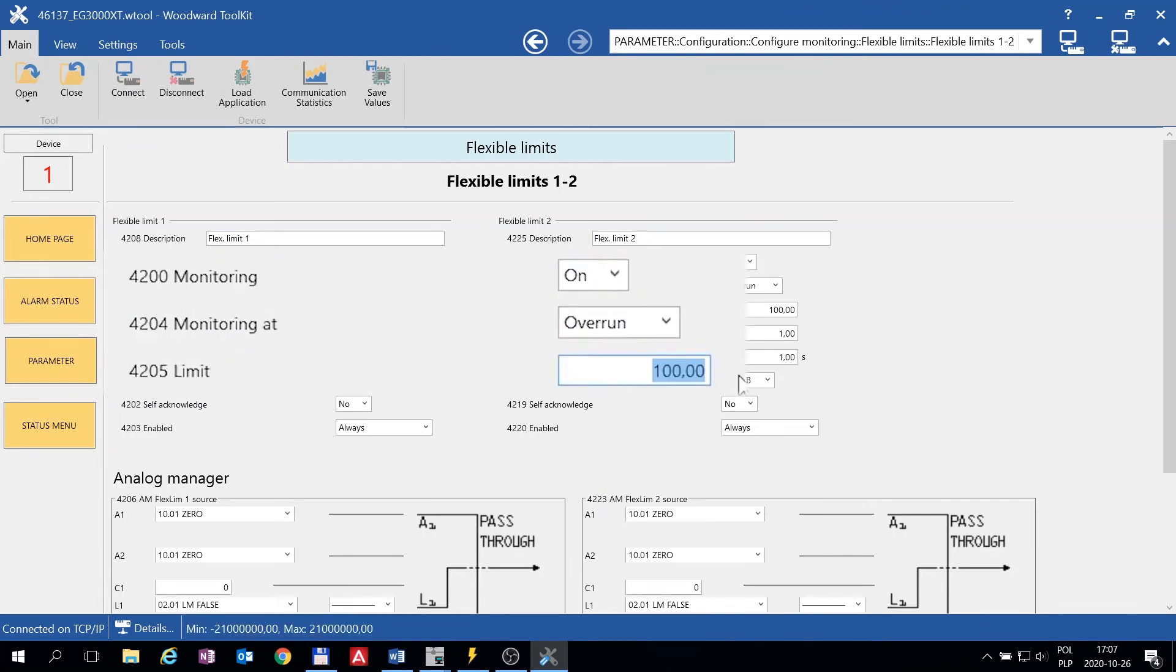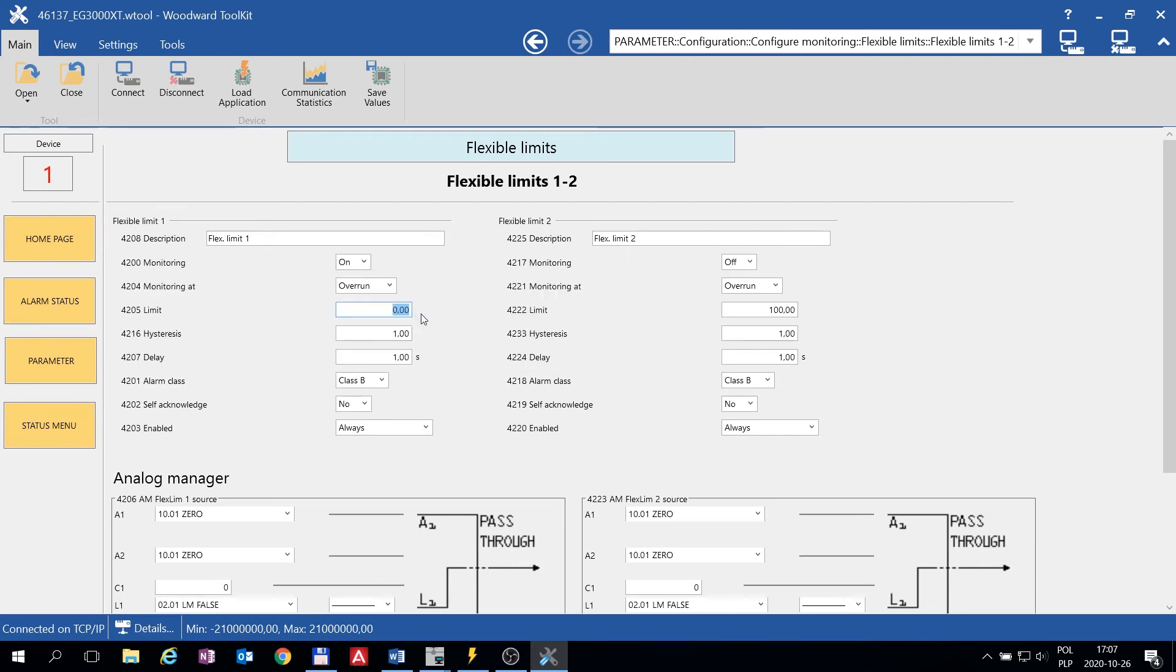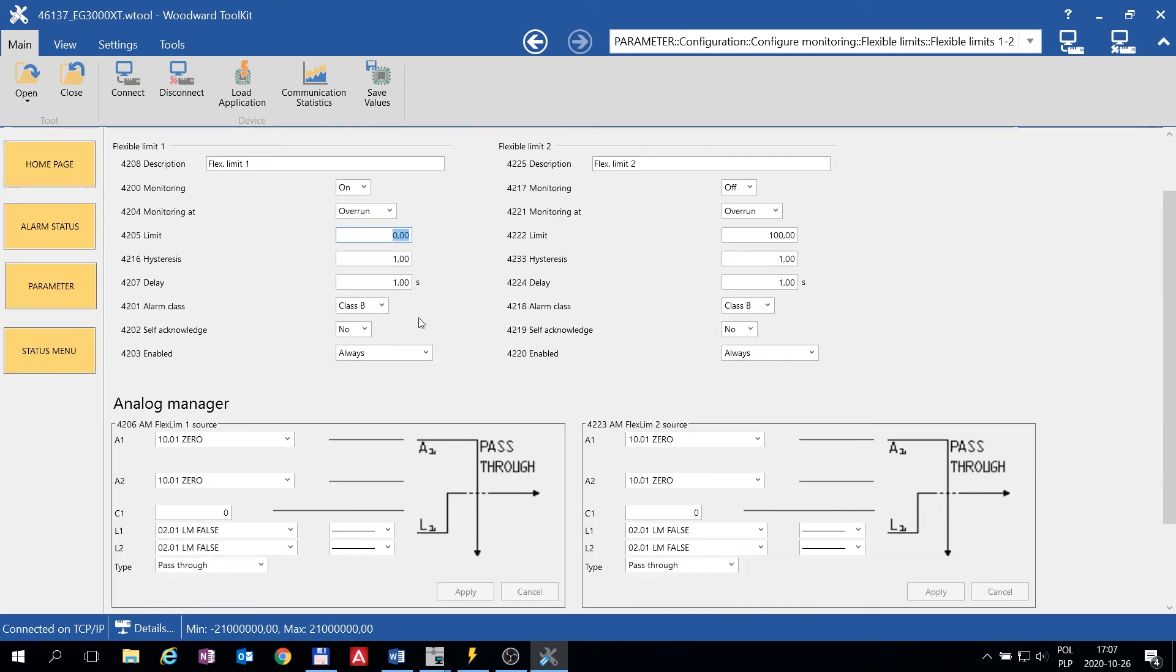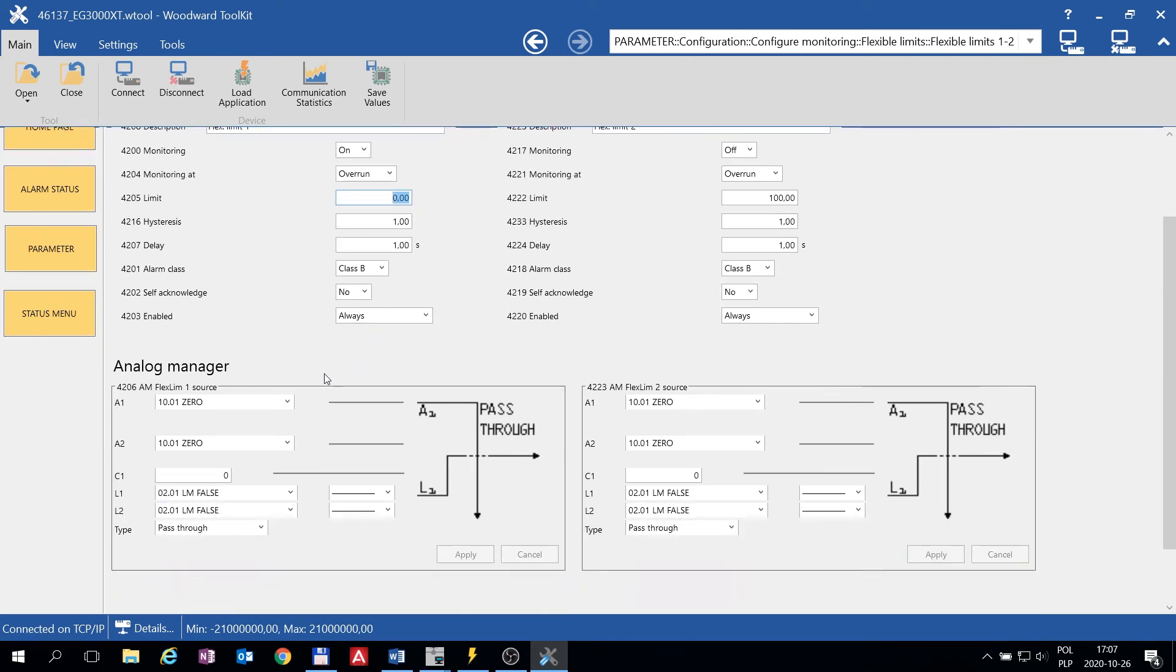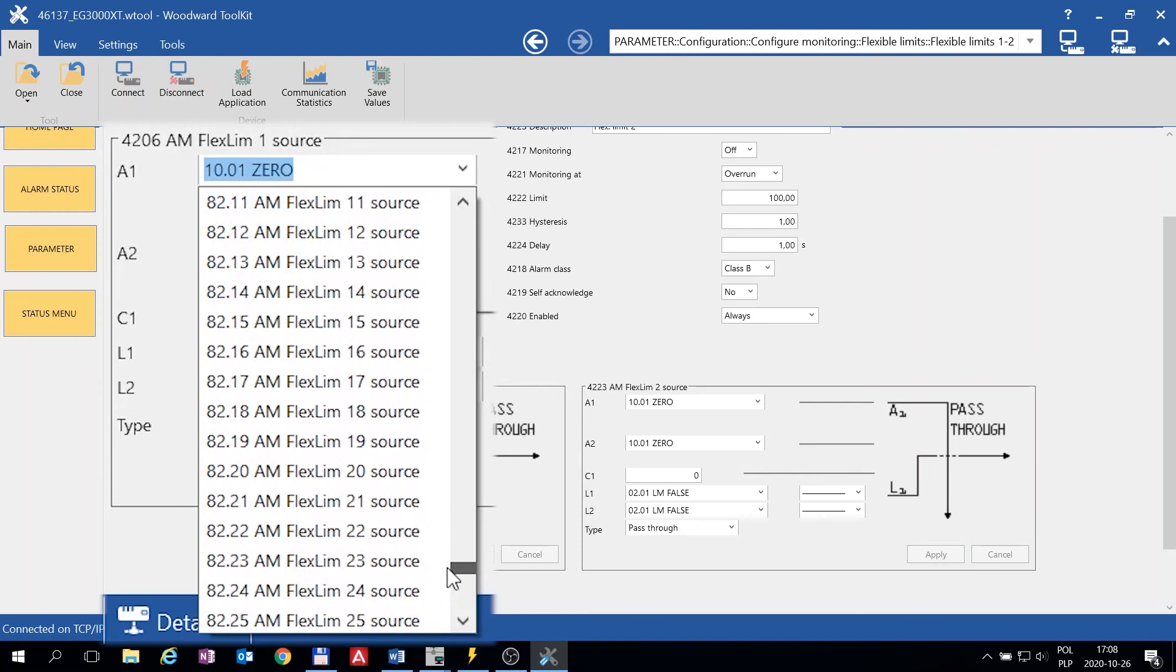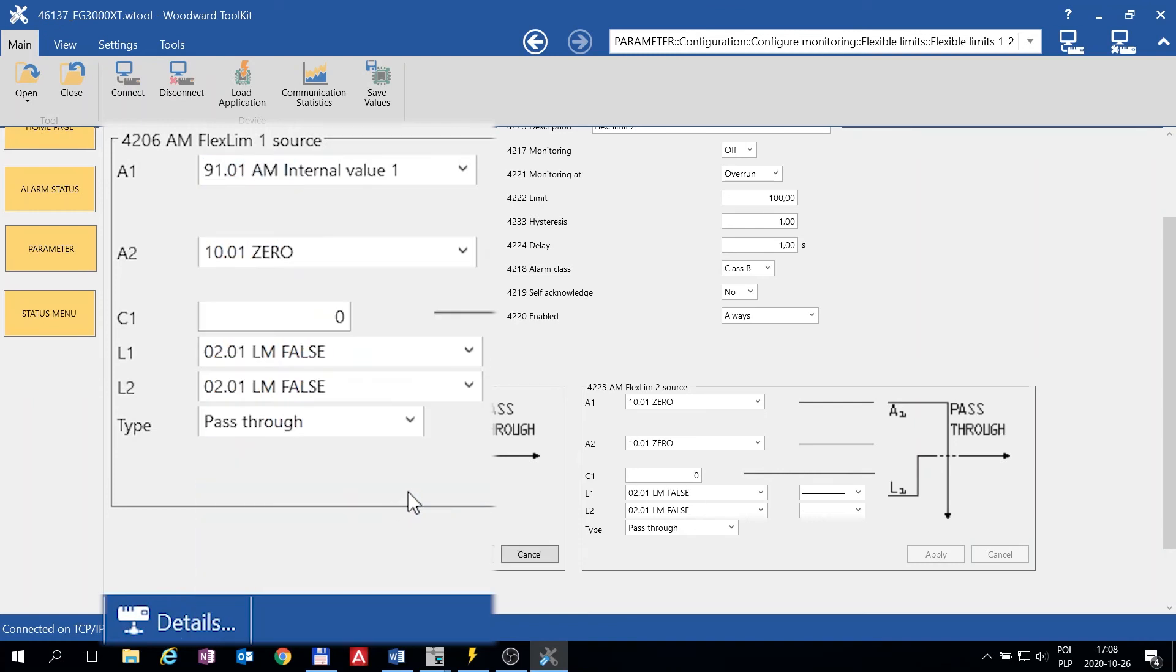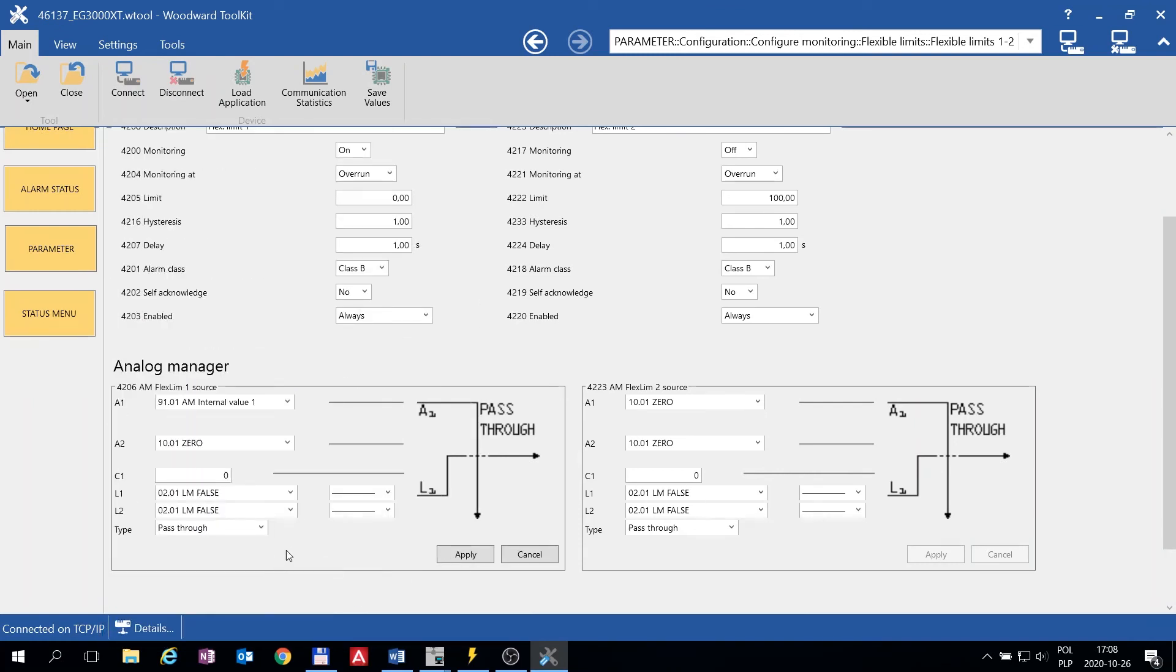Because when we are above 0 Kilowatts, that means we are exporting power to the grid and we want to have an alarm. As a source we should choose our newly configured analog value, and click Apply.